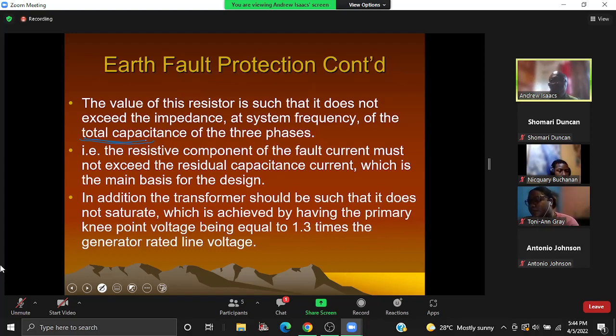And as pointed out here, we are able to avoid saturation if the knee point is equal to 1.3 times the generator rated line voltage. And you'll see that factor coming up in the calculations. All right, just remember this 1.3. Now, the question is, why 1.3? Why not say 2 and be on the safe side?